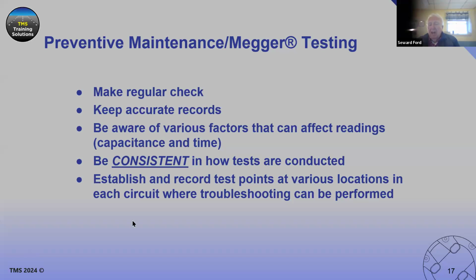Be consistent in how the tests are conducted. You can't compare the previous test with this test if you're not consistent in the methods you use to do the tests. And then establish and record test points at various locations in each circuit where troubleshooting can be performed. You can have points in your circuit where you have access to the circuit. It may be in a transformer housing, a base can housing, where you can get in there and isolate the circuit or a segment of the circuit, and test that segment to see what's happening with regard to the meggering there, and you'll see a trend developing.